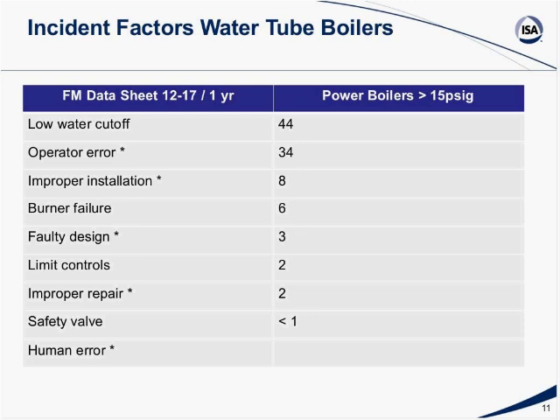Improper installation, where the system may not have been put in according to the design and the design requirements. Burner, that was 8. Burner failure is 6. Faulty design, there was just 3, but that again can be very key. Limit controls: the controls were limited and did not give enough detail or operate properly. Improper repair, there were 2. In other words, there was a repair to be done, but it was not done properly. There's less than one more safety valve failure, that'd be your relief valves.